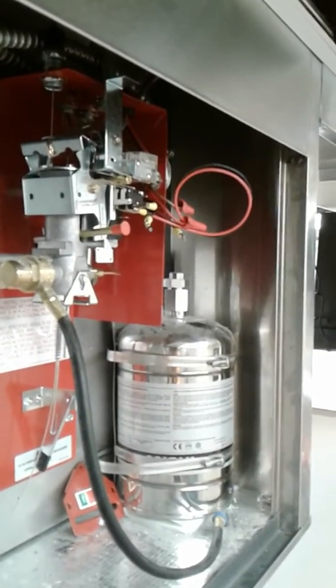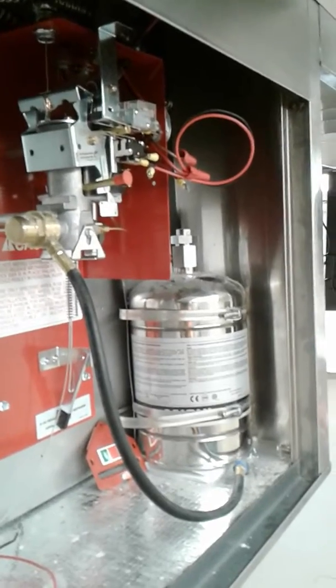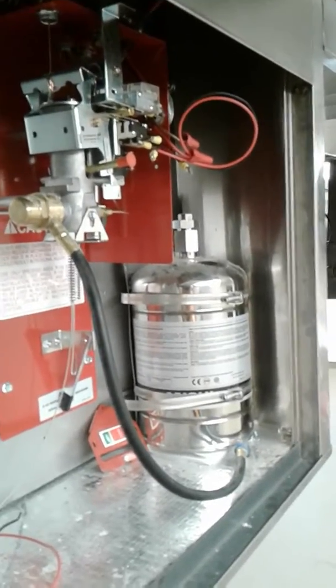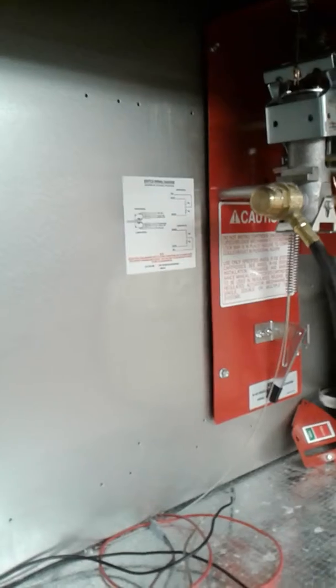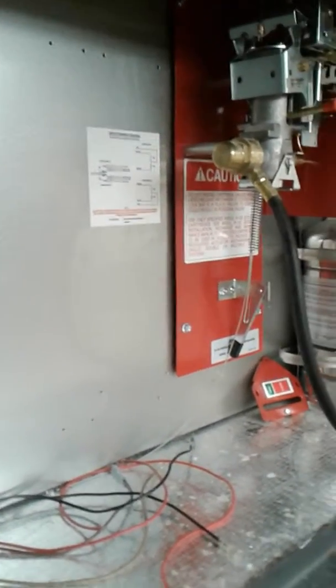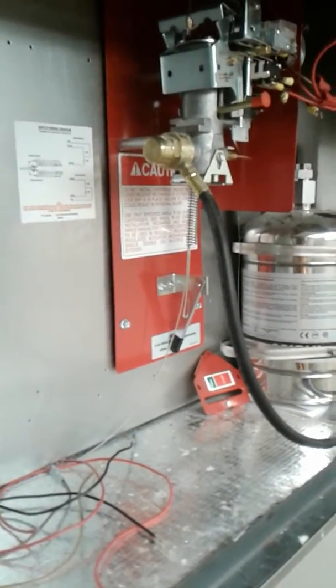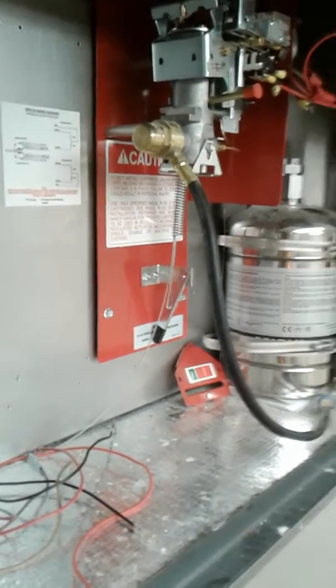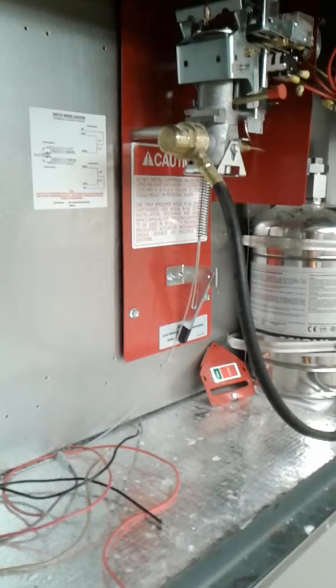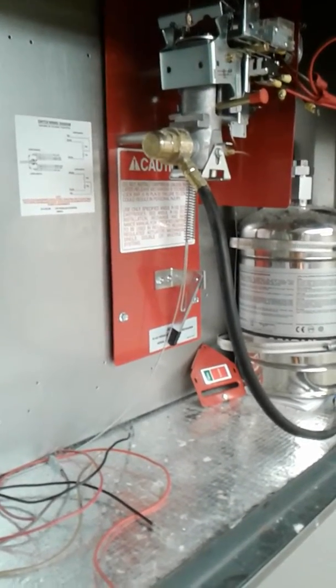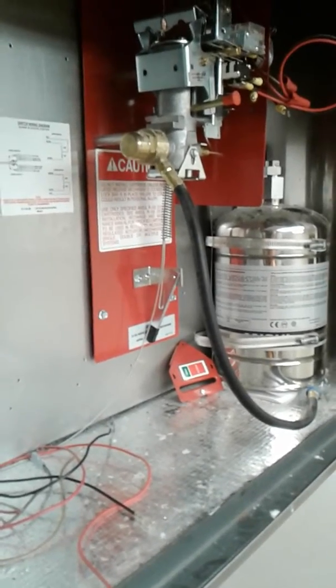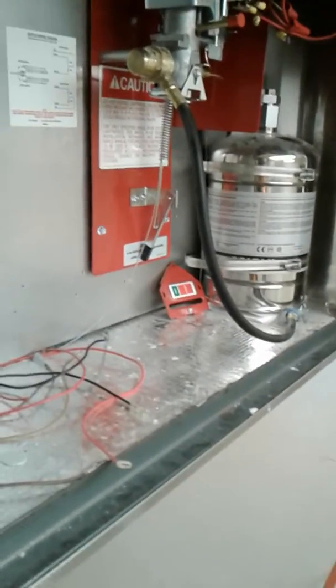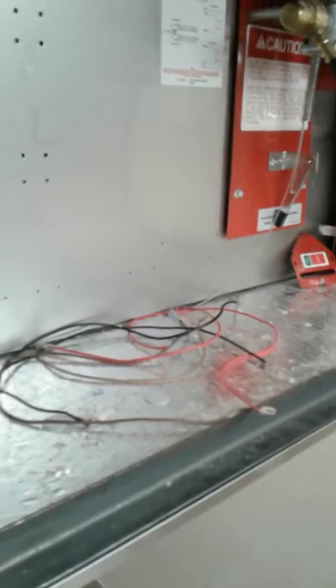And they're normally open and normally closed is actually backwards from it. It was so confusing the whole way through it because one person's saying one thing, one person's saying another thing. You can look on the side of the micro switch and there's a schematic that is opposite of that schematic right there. Because in their mind, normal condition is when this thing is armed and cocked. Well, it's not really a normal position because the spring's compressed and it's having tension put on it. A normal position would be completely relaxed state. So, they've got their idea of normally backwards. But, because they're fire alarm guys, they're not electricians or whatnot.